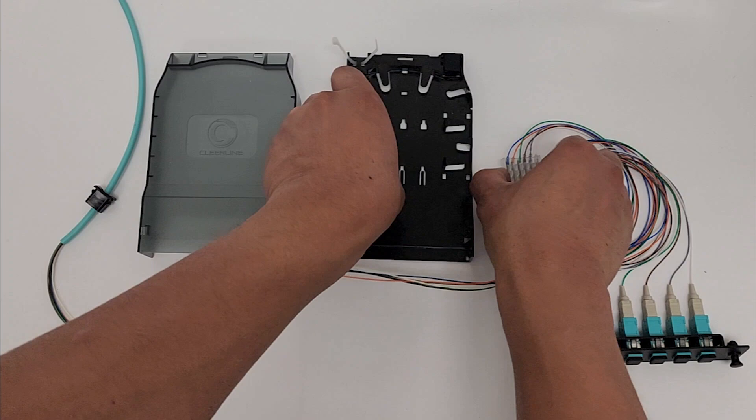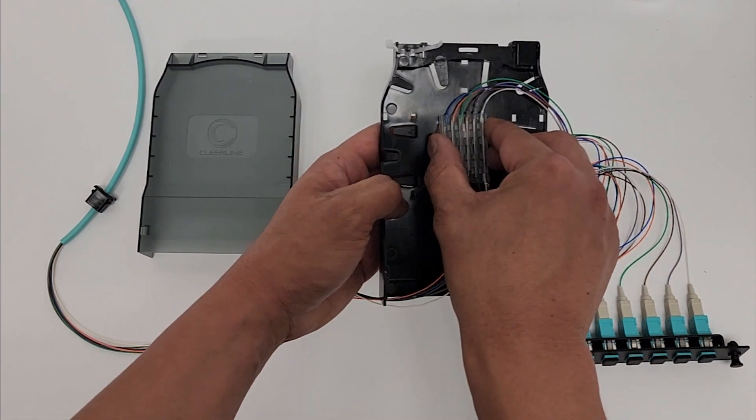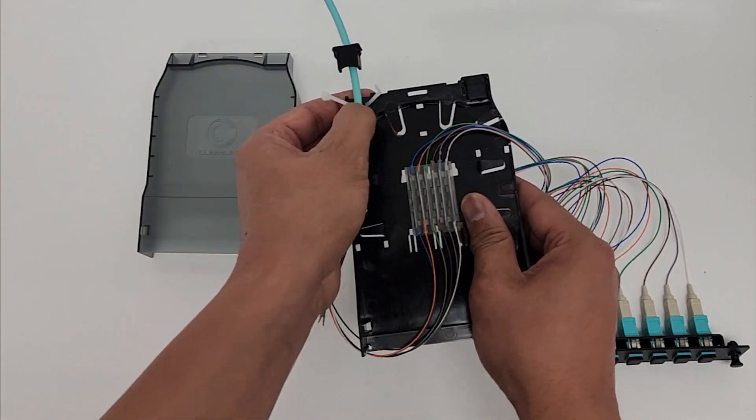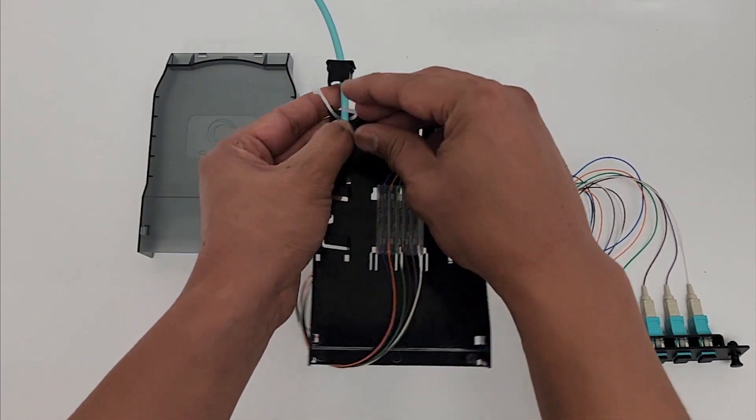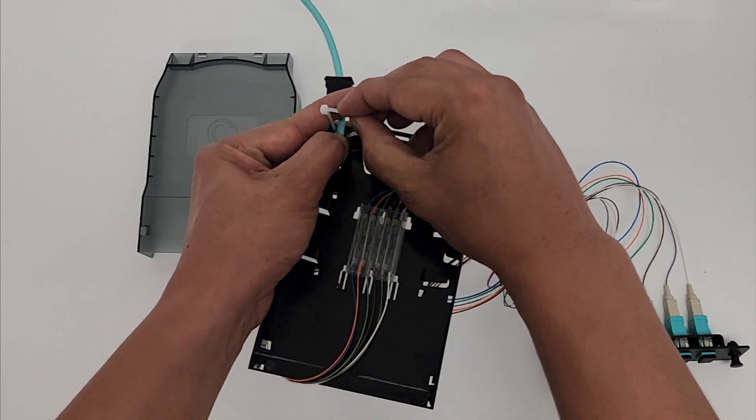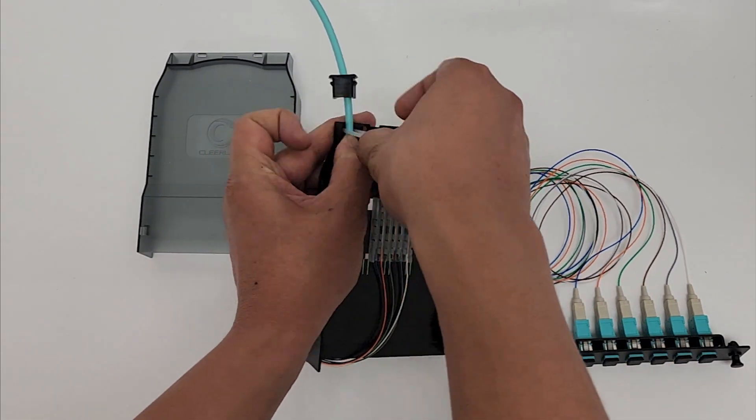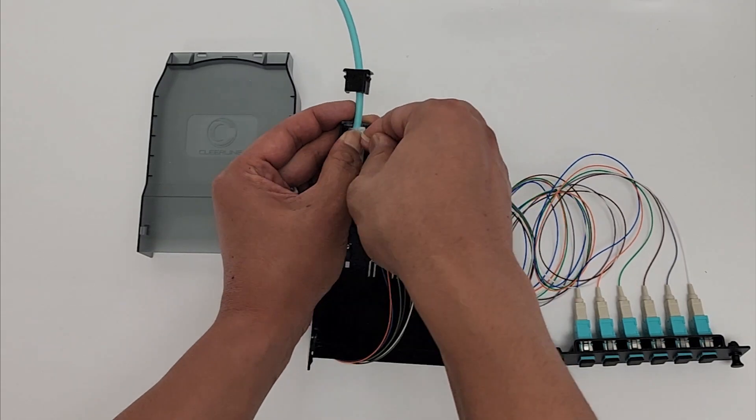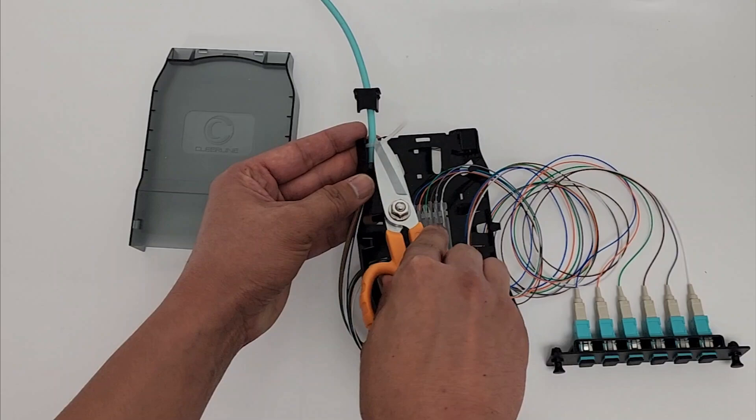Next, install the splice tray onto the bottom housing. Ensure the pigtails exit the splice tray towards the rear and the incoming fiber towards the adapter plate position. Now, secure the incoming fiber with zip tie, taking care not to overtighten, and route the incoming fiber clockwise.